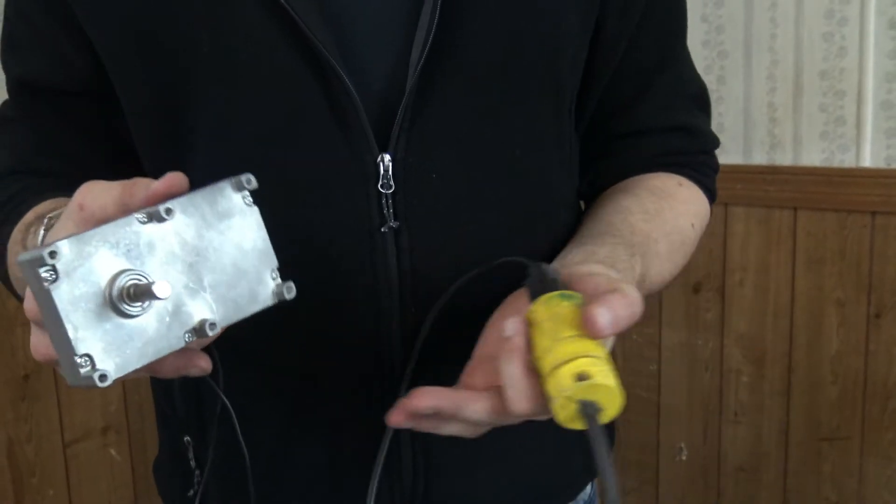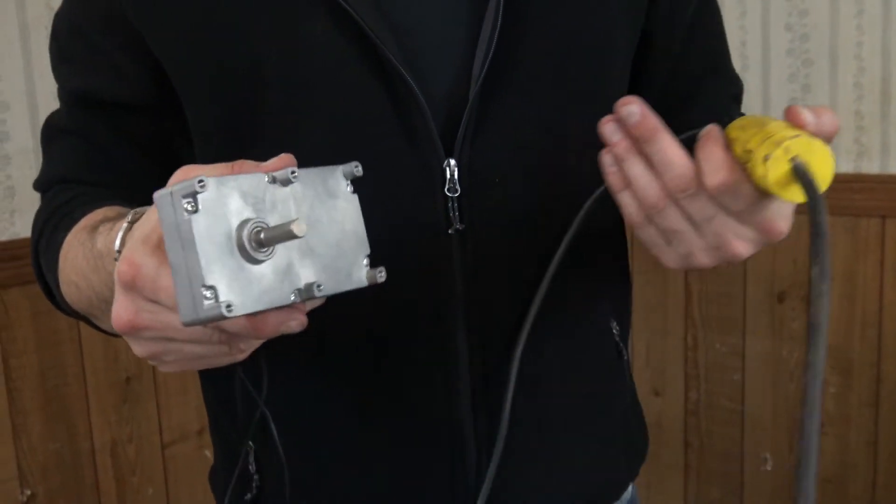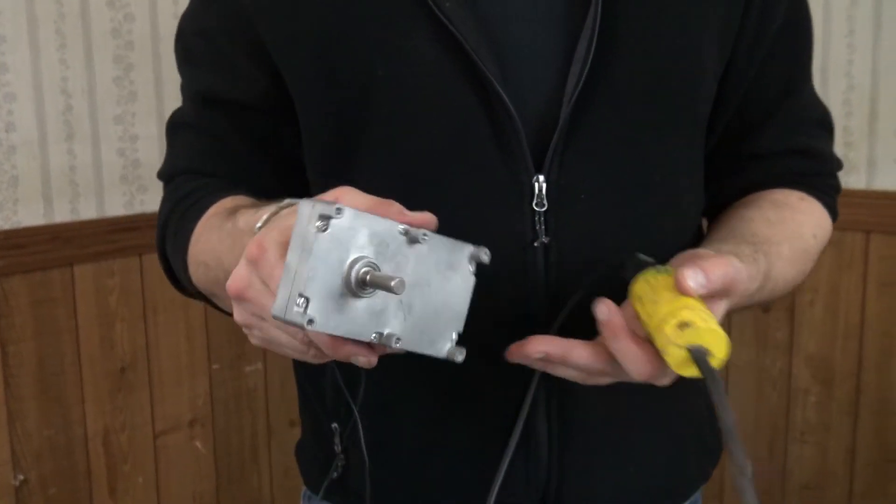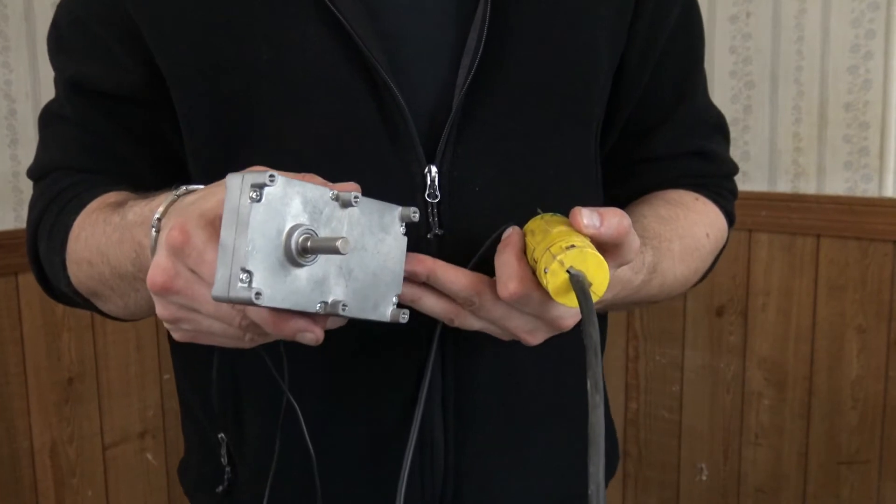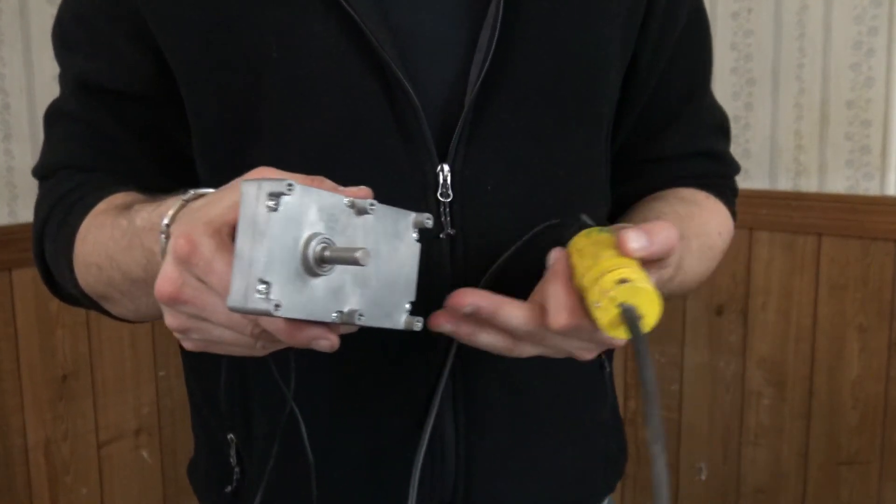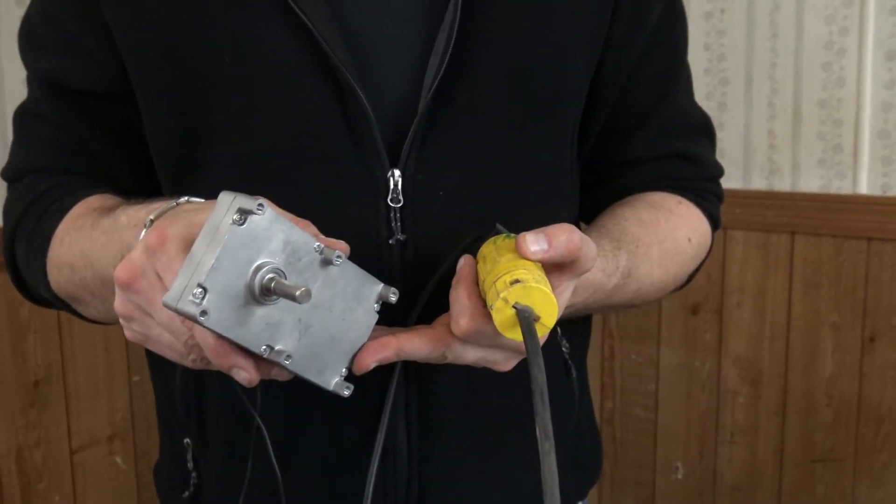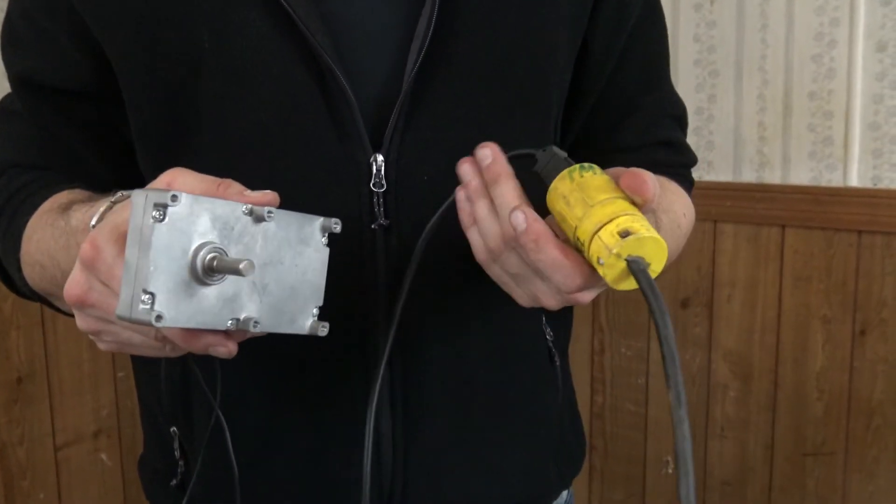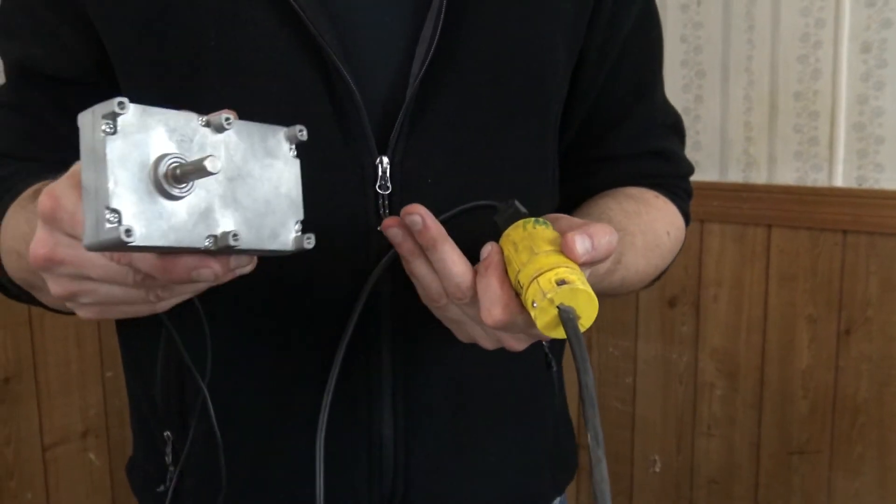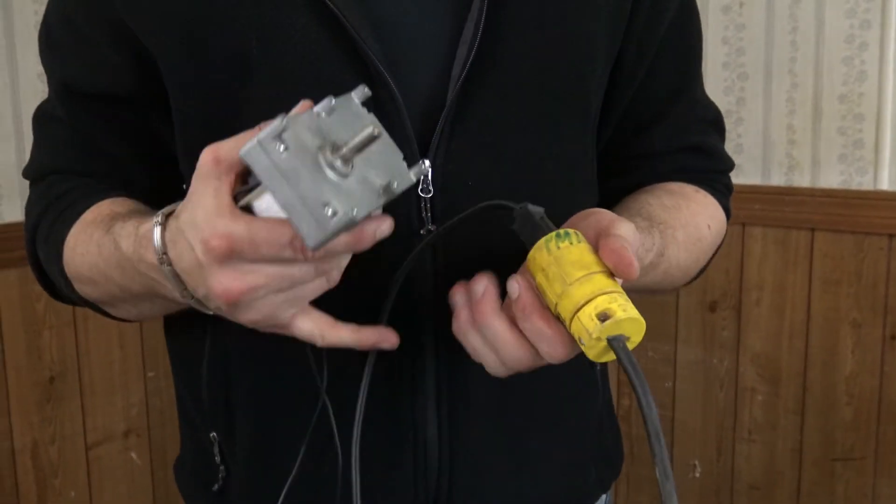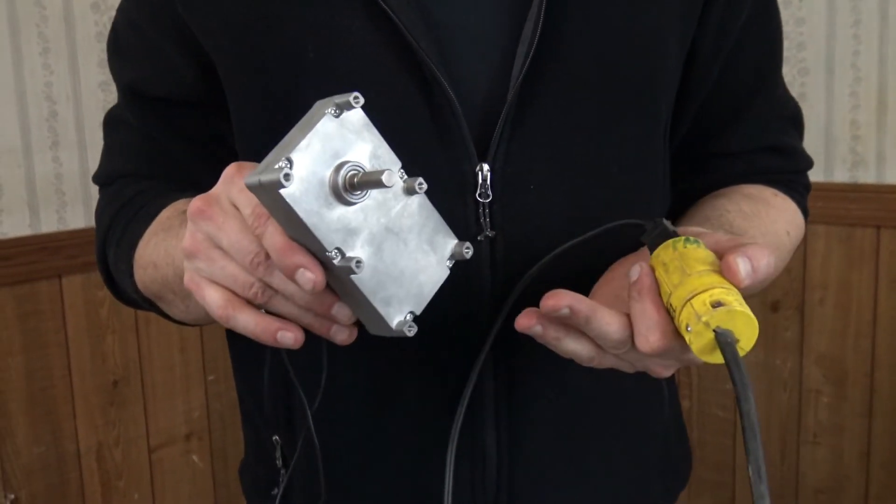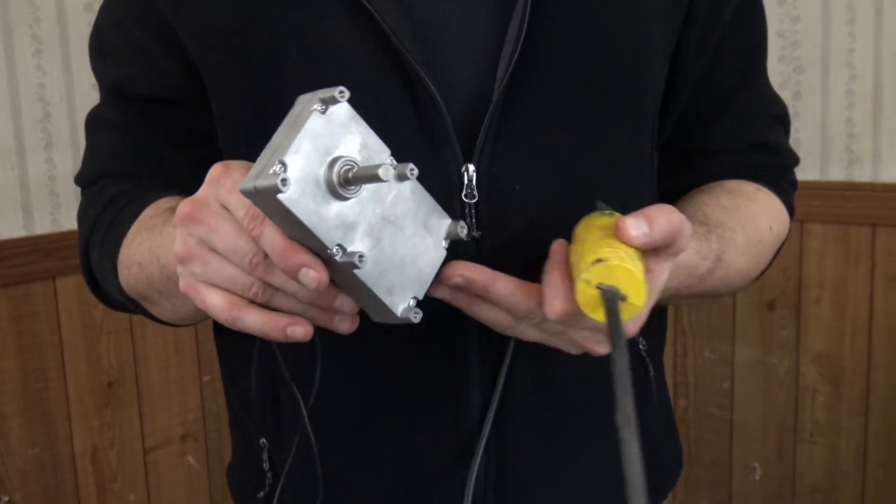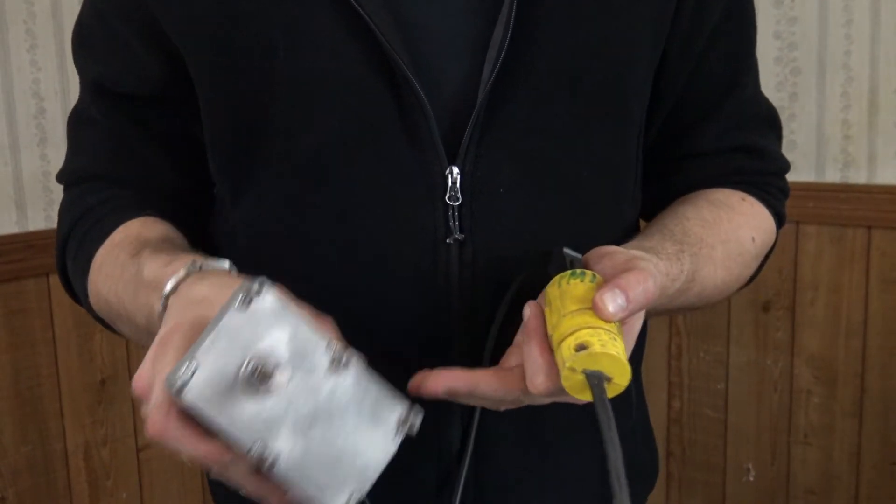So again, whether it's an auger motor, a combustion fan, or a distribution fan, if you need to direct test a motor and make sure that it's not one of the safety switches that's shutting it off, by creating a test cord like this, we can test our motors directly with 120 volt power. And again, it's going to let us know either A, it's working or B, it's bad.